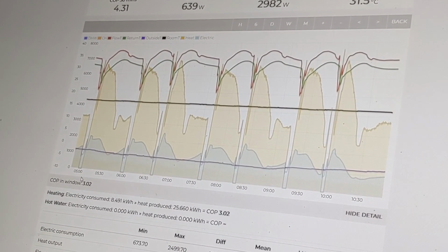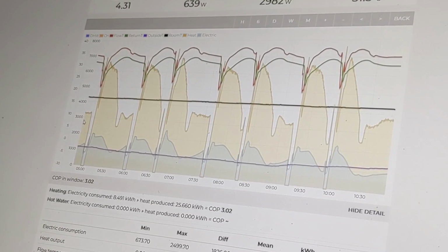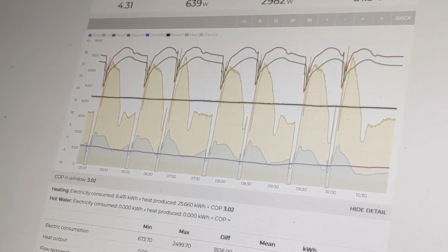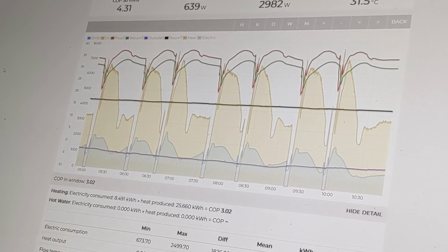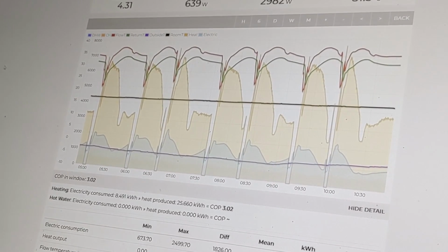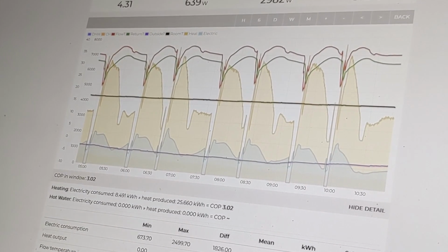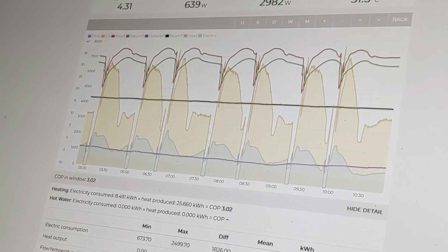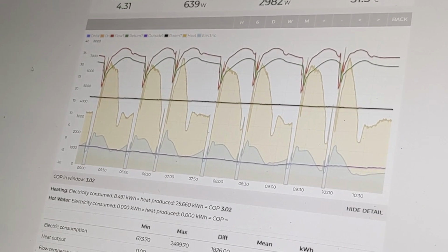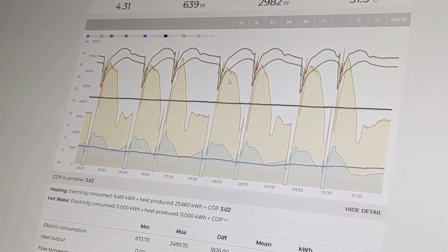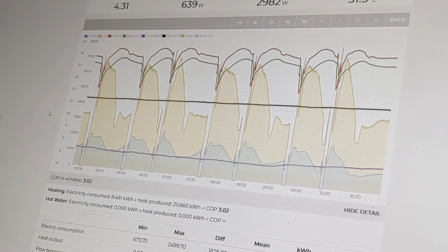But if one room was heating up quicker, the thermostat in that room should trip it, unless it's in your core area. Yes, unless it's in the core area. So for a peripheral room like a bedroom, you could use a TRV, a thermostatic radiator valve, to control the temperature. But in your living areas, you don't want the system turning on and off. You want it running constantly. So balancing the different rooms in your living areas is what you should aim to do.